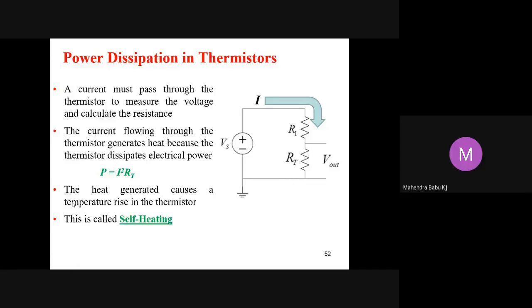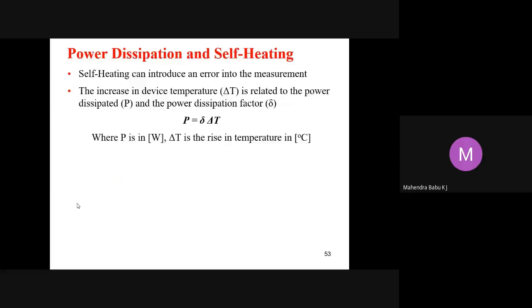Then you may ask whether this self-heating is good or bad. Definitely, self-heating is not good, it is bad. So why is self-heating bad? Self-heating can introduce an error into the measurement. This increase in device temperature is related to the power dissipated and the dissipation factor delta, where P = delta × ΔT, where delta is the dissipation factor and ΔT is the increase in device temperature. P is in watts and ΔT is the rise in temperature in degrees Celsius.